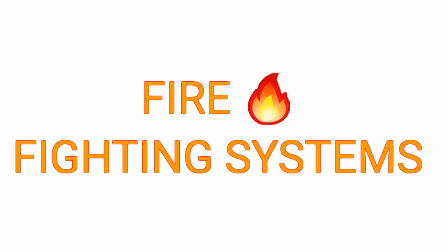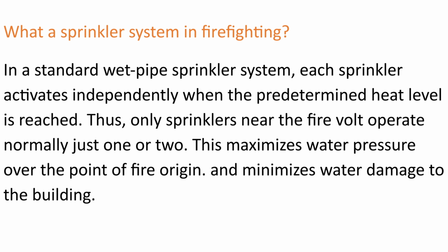Firefighting, general, question and answer. What is a sprinkler system in firefighting? In a standard wet pipe sprinkler system, each sprinkler activates independently when the predetermined heat level is reached. Thus, only sprinklers near the fire source operate normally, just one or two. This maximizes water pressure over the point of fire origin and minimizes water damage to the building.